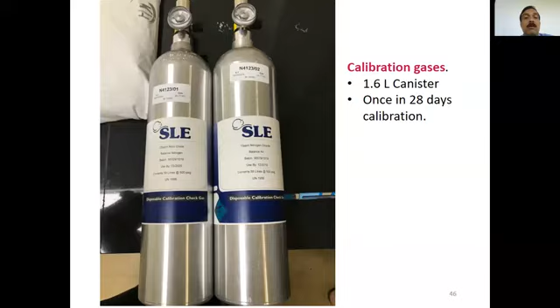That's the reason it's very important, when we buy this equipment, to ask what maintenance cost is required, and whether backup with the biomedical engineer is available. Otherwise, most of these units could be useless when we buy them and are not going to regularly service this nitric oxide system. And here, if you can see, once it's calibrated, nitric oxide shows calibrated to 25 parts per million, and this is ready to use.